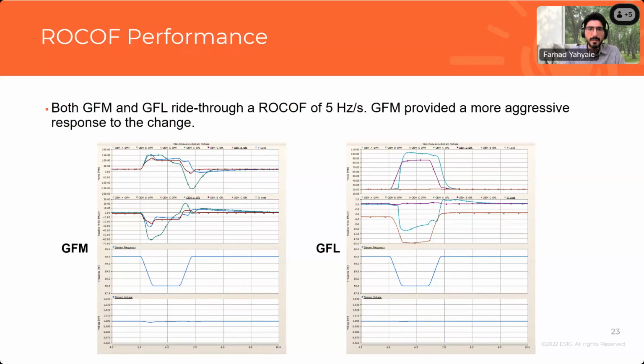We also assessed rate-of-change-of-frequency (ROCOF) and phase angle jump. For both GFM and GFL, all models were able to ride through a ROCOF of 5 Hz per second. The only difference was that the GFM provided a more aggressive response to the change than the GFL.